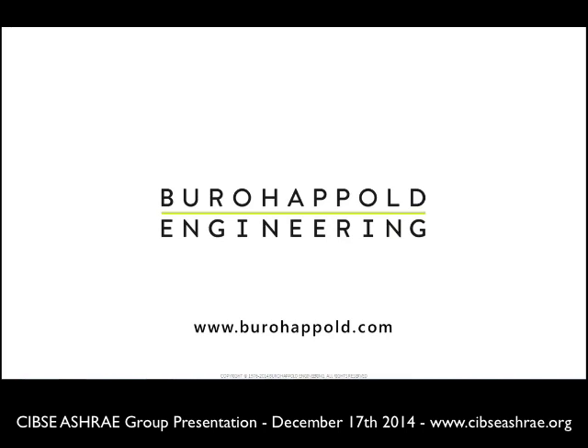Is it difficult to actually determine the appropriate design conditions for the arid zones? Depending on the location, if it's in the larger city areas covered by ASHRAE, we would tend to use ASHRAE as a basis. But often we are designing outside of places like Riyadh, or further east in Dhahran or Dammam, and other areas where there's a temperature variance from the capital city. We would use ASHRAE as the nearest basis, but we'd also refer to the nearest Saudi meteorological data to help inform us of the variance in weather data from the CIBSE and ASHRAE codes.